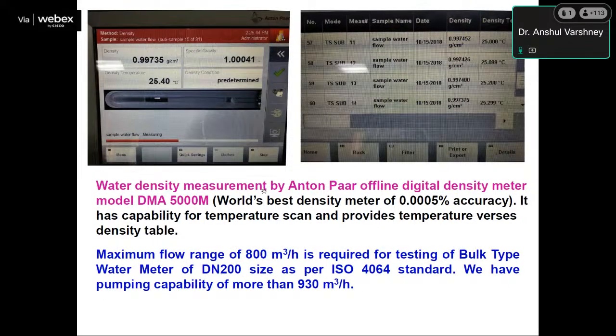We are using an offline digital density meter for water density calculation. It is the world's best density meter, having an accuracy of 0.0005%. It has the capability for a temperature scan and provides a temperature versus density table.